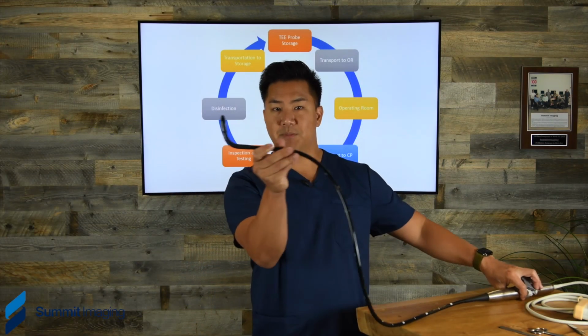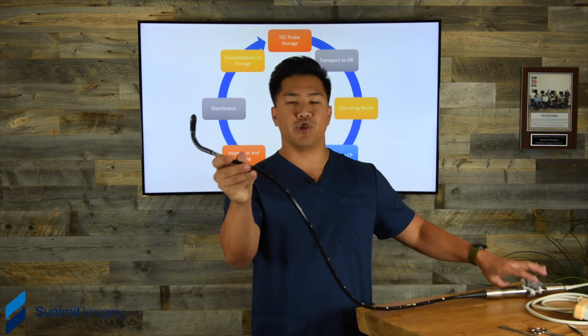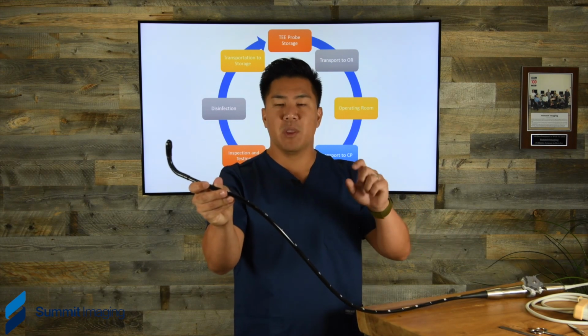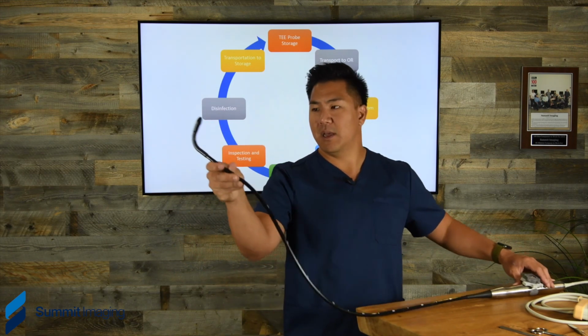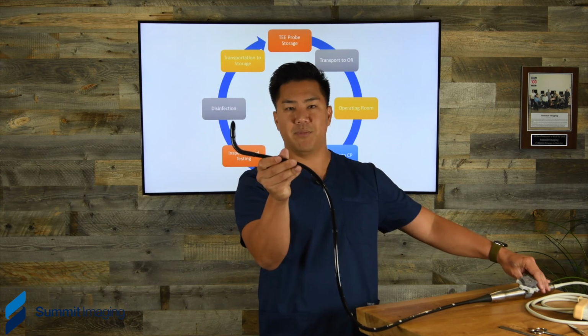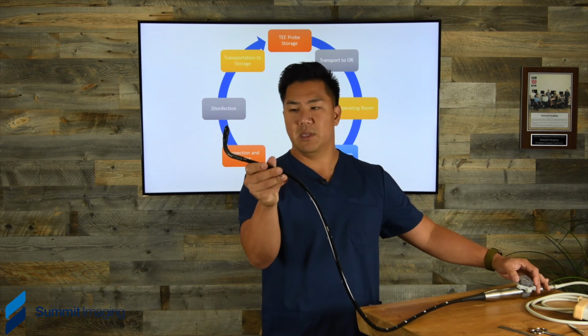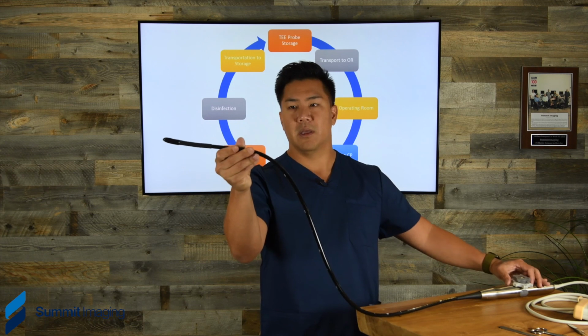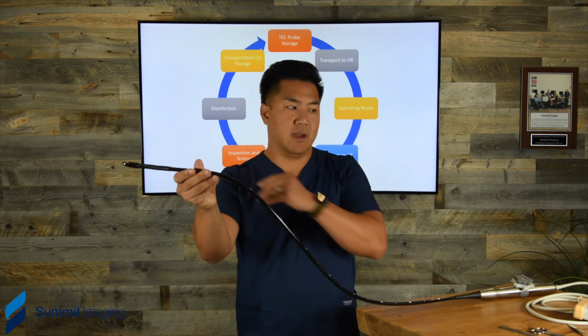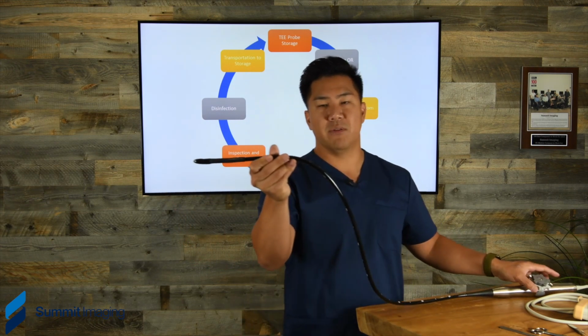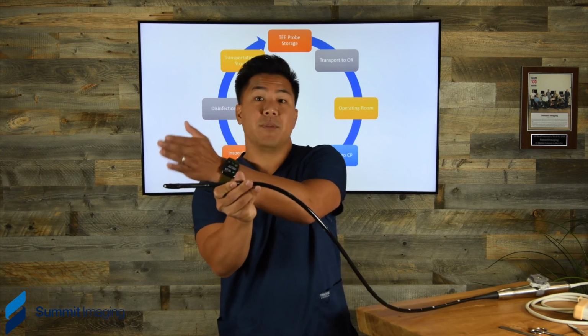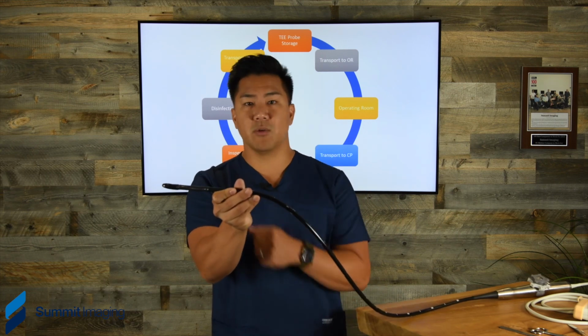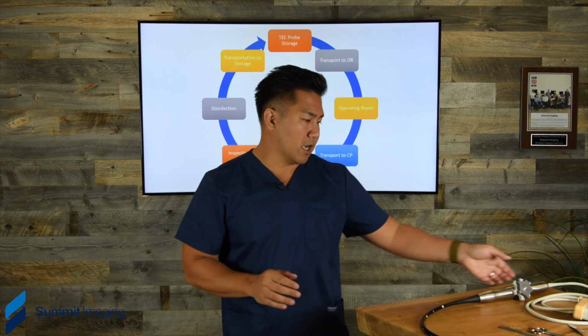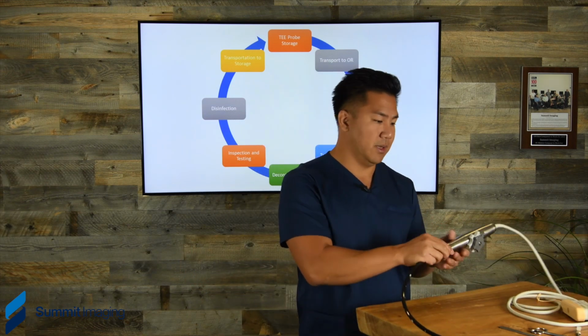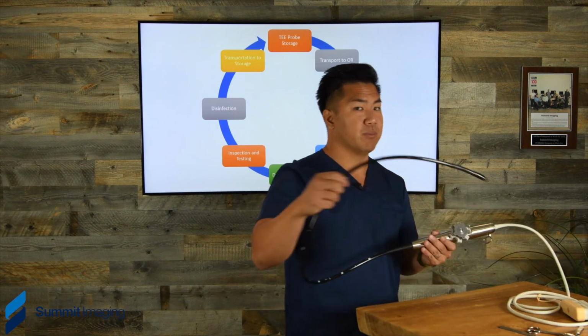So as they're dragging it out, because there's pressure to keep this at 90 degrees, it will drag against the back of the molars. And so what we recommend, talking with the technicians out there, all you gotta do is unlock it and let the probe relax straight. And as you pull it out, it prevents the molars from hitting the most sensitive part of the probe, which is that crystal. Another item to talk about is where the handle is actually stored during a procedure.